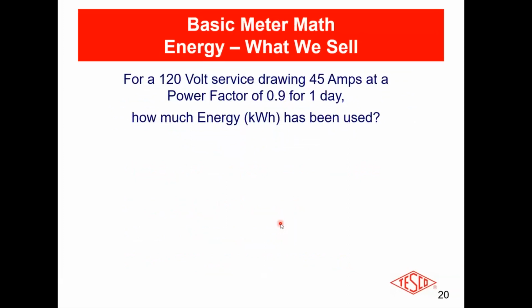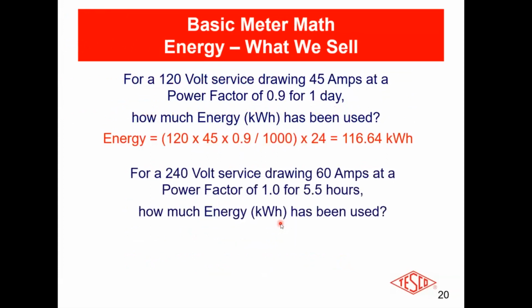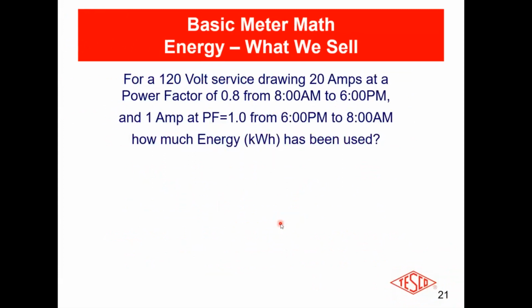All right, 120 volts, 45 amps, power factor of 0.9 for a day. That's 24 hours. How much energy are we using? 116 kilowatt hours. Again, if I've got a power factor of 1, how much am I using? 79.2 kilowatt hours.